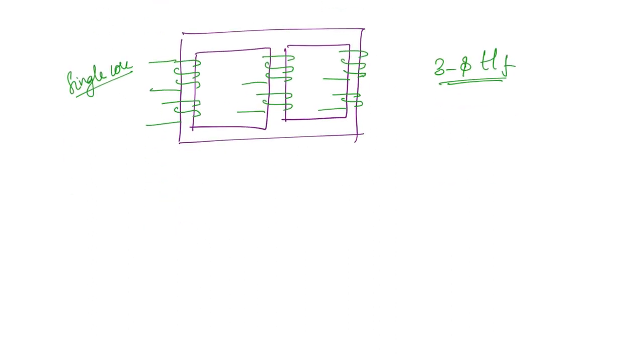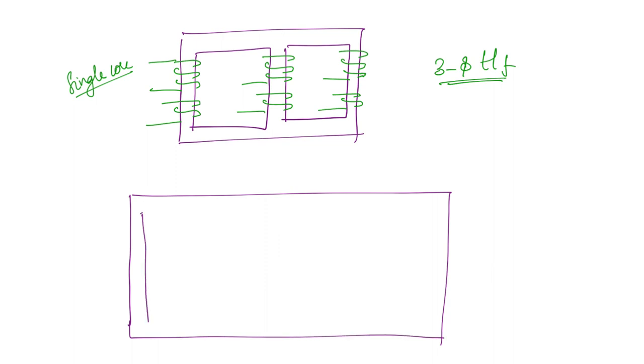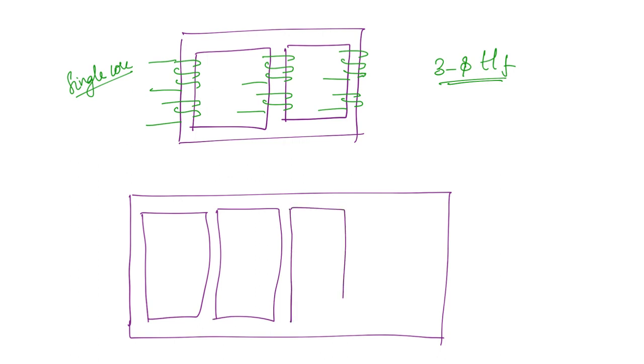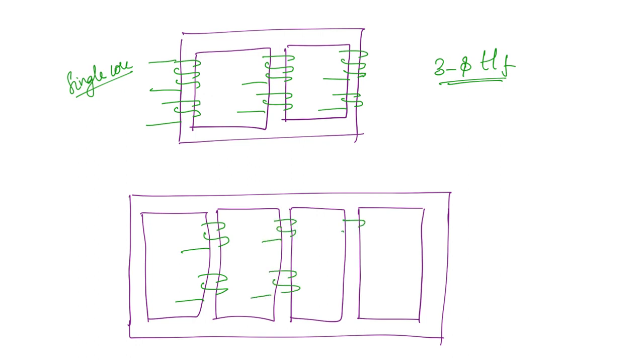In a shell type, all of the windings are wound on internal legs. Here you have one internal leg for one phase, this is for the second phase, and finally for the third phase. The windings are arranged as phase 1 primary and secondary, phase 2 primary and secondary, and phase 3 primary and secondary. So this is the shell type single core, and this is the core type single core.